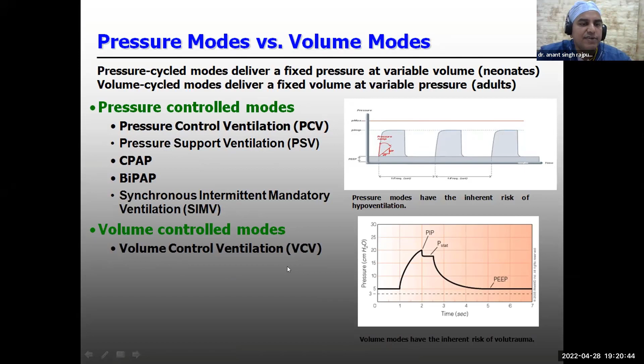Okay, so this is a graph which we need to understand in a proper way. In this first graph, you can see the pressure is variable. Okay, this is a volume control mode. When the pressure is variable, it is not fixed, it becomes a volume control mode. But if you look, the flow goes up and the flow is constant. So you get a quadrangular graphic in volume control mode, right? Expiration in both the modes is almost similar. You cannot differentiate based on expiration. The ventilator has nothing to do with expiration basically. It is the leftover time, right? Now, in pressure control mode, you have a quadrangular graphic, right?